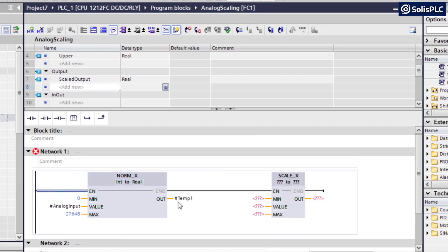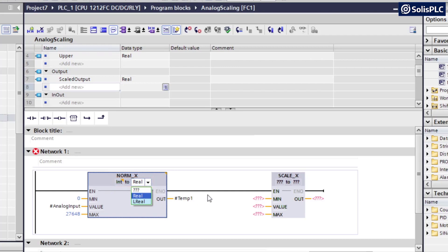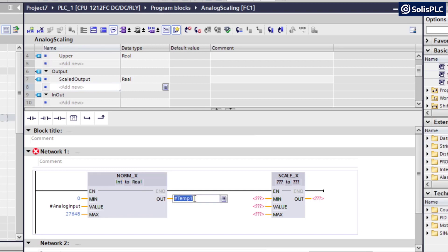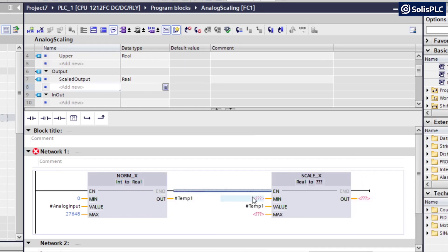And the output, this is going to be our temp value. So this is just going to convert from that integer into a real. What's really interesting is that in TIA Portal, you can specify from which value to which value you're going to convert depending on the tags that you're using on your instruction. And so once we scale to this temp 1, we can then proceed to scale it up to the value of our choice.